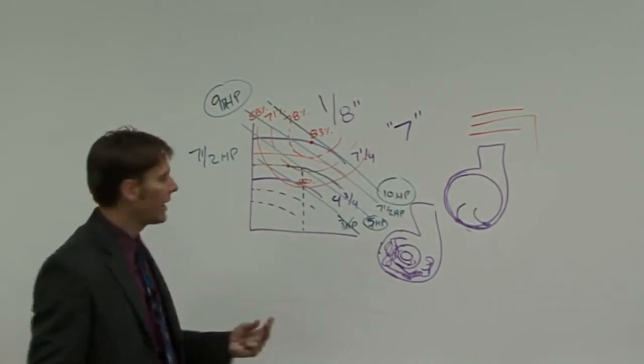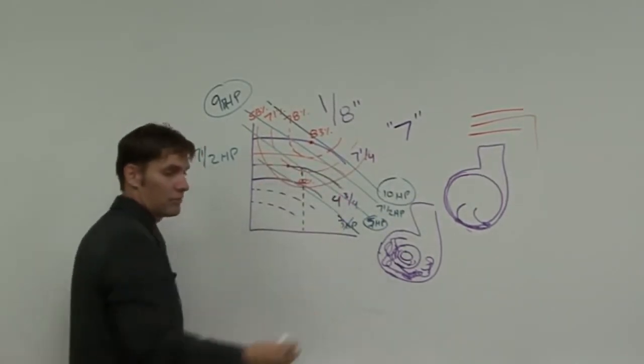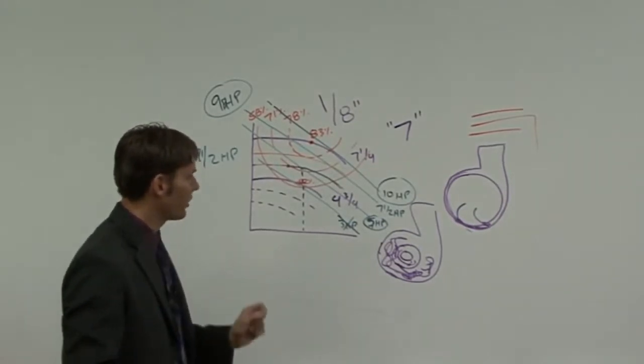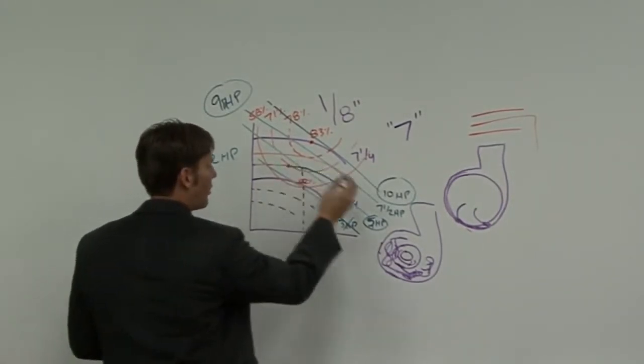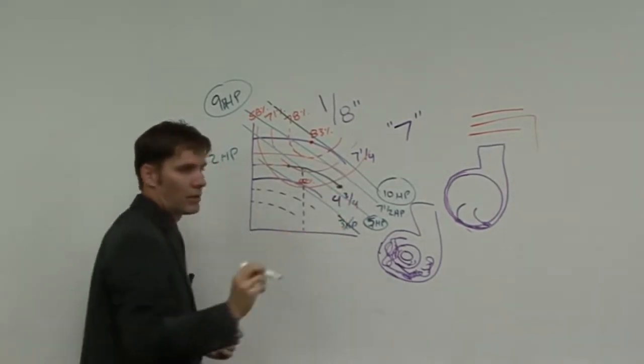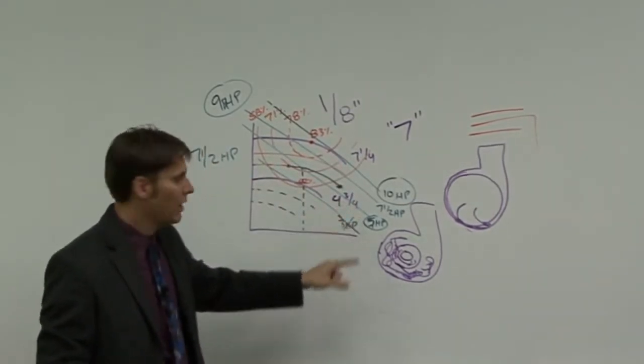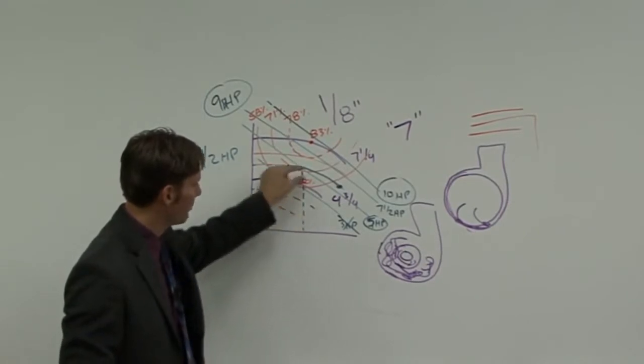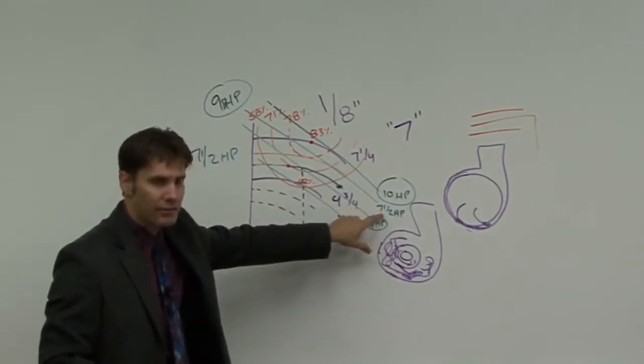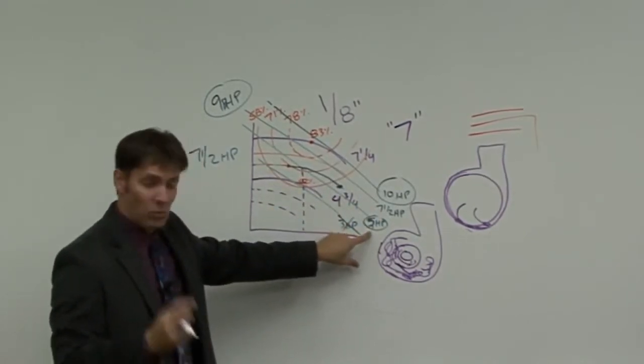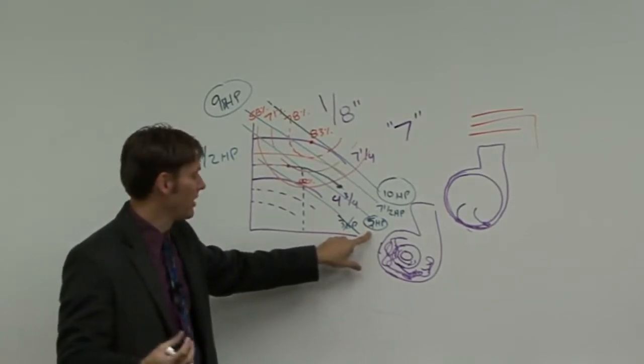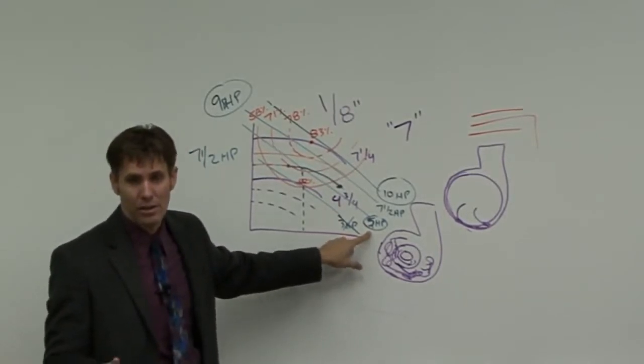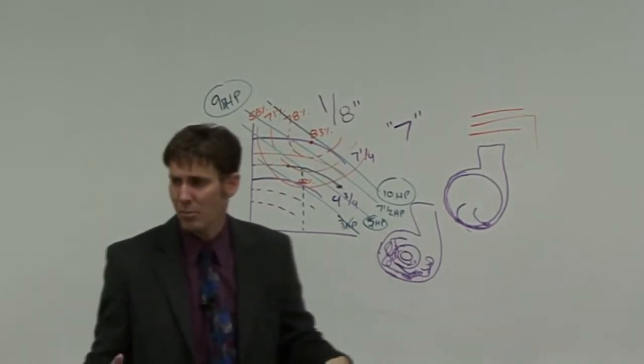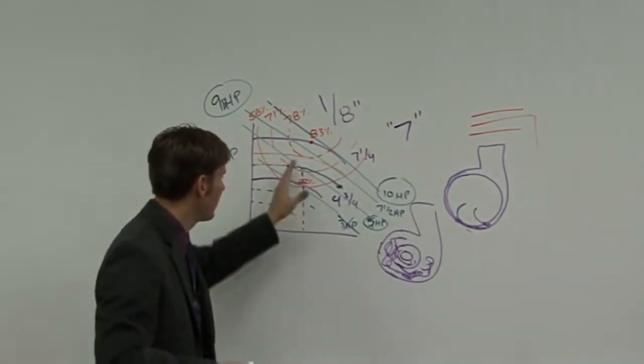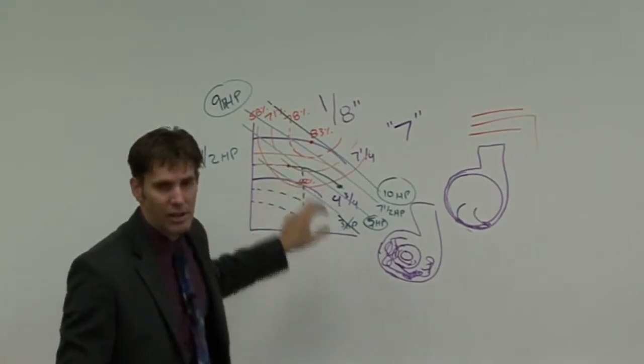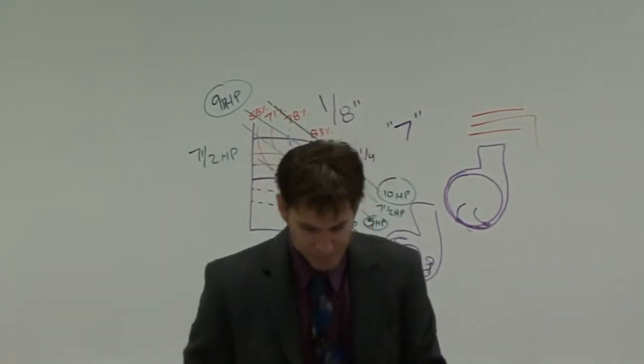So when engineers are selecting pumps, they look at this quite often. And unfortunately, I believe too many engineers always pick a motor that's non-overloading across the entire pump curve. So if an engineer were to pick this pump or this motor, he would size a 7.5, when in reality, when we look at the realistic application, they'll never exceed this 5 horsepower. Now you can't use that as a blanket statement, but it's fairly safe to assume, depending on the difference here. And we'll talk about that more in just a little bit.